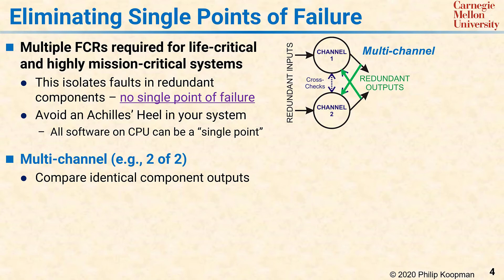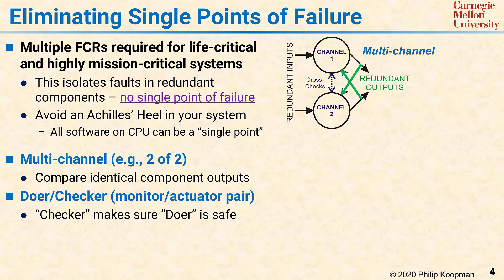Each channel is designed to be a separate fault containment region. Any mismatch between channel outputs indicates a computational failure. A two-of-two architecture can be extremely effective at mitigating hardware faults. However, because the same software is running in both channels, the software must, for practical purposes, be perfect — for example, by developing that software to a high safety integrity level.